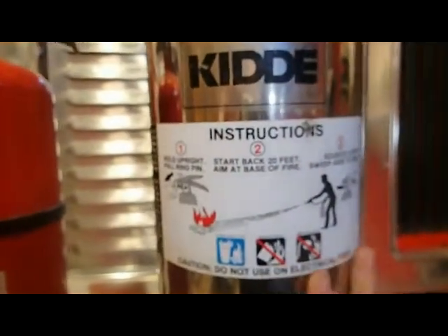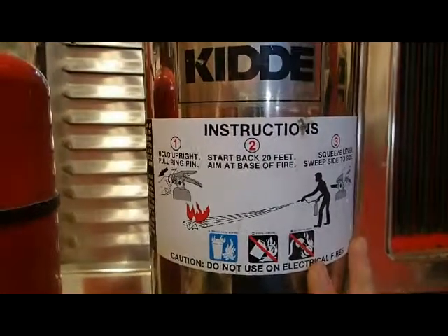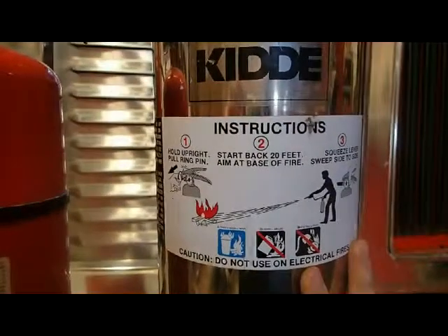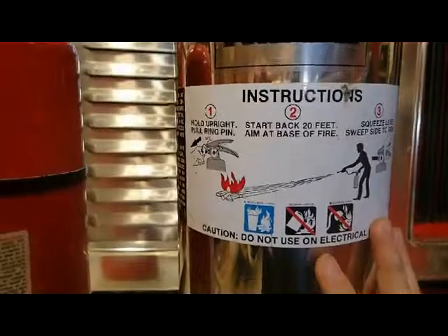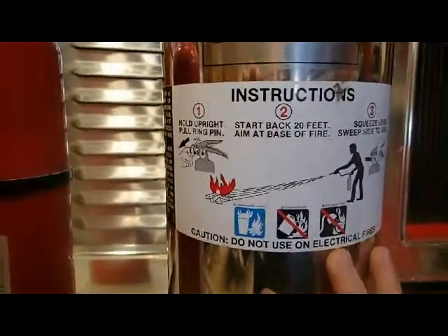And the way this one works is water is actually the best conductor of heat you can find out there. When it turns from water to steam, it's actually going to expand 1,700 times its original size, and that rapidly cools the environment and absorbs all the heat, and it's going to take away that part of the fire triangle that allows the fire to keep burning.